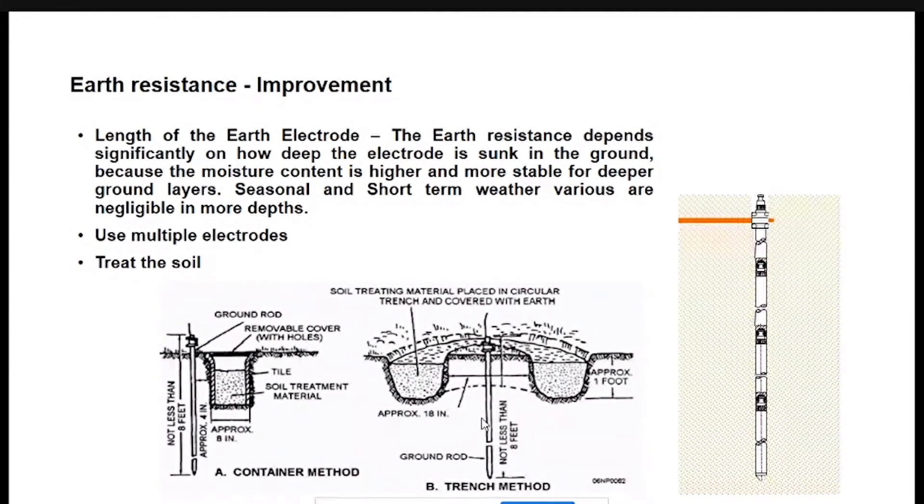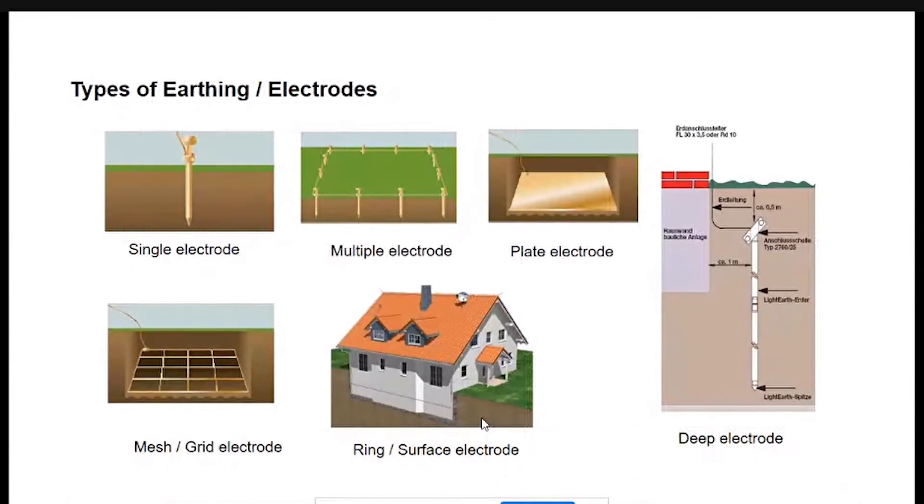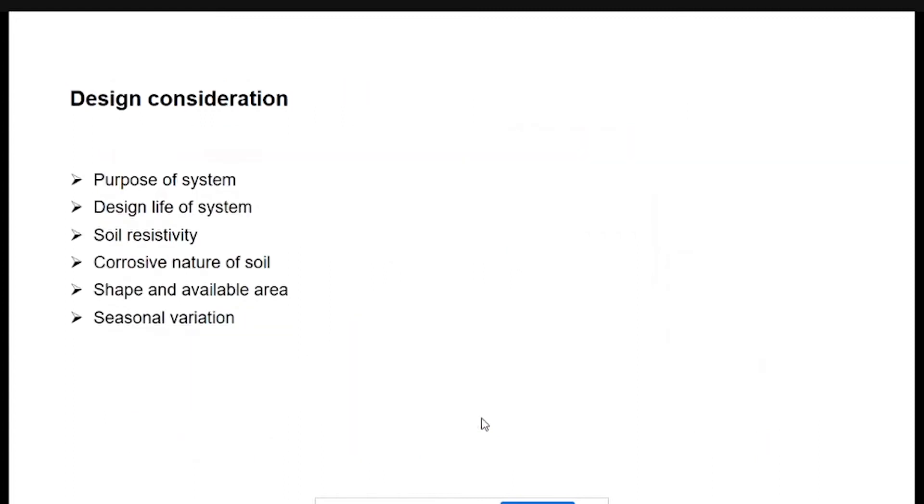There are different methods of earthing practiced, and the best method to get better resistance is the deep driven electrode method. If your resistance is important, then you have to drive the electrode deeply. But if your step and touch potential is important, then the design of earthing should be more of horizontal earth electrodes like plate electrode or mesh electrode.